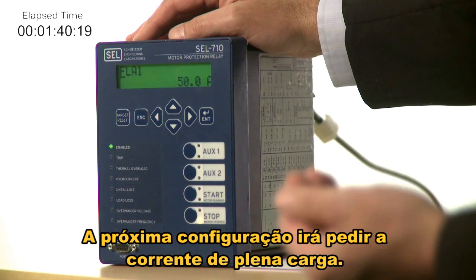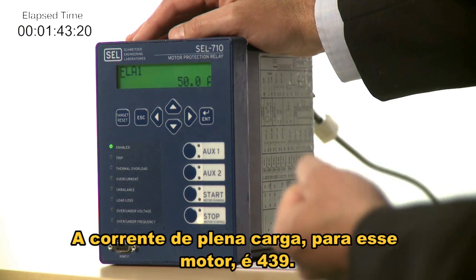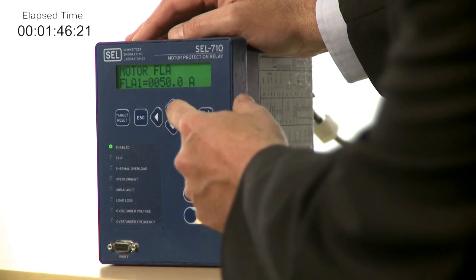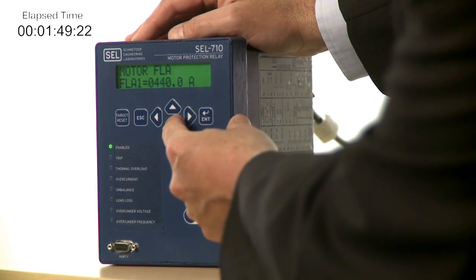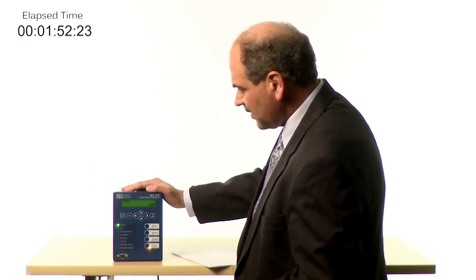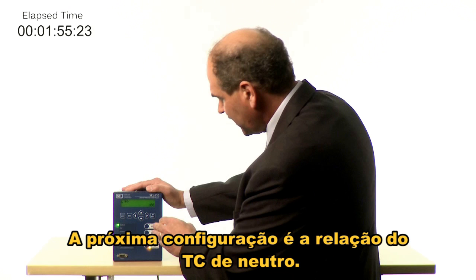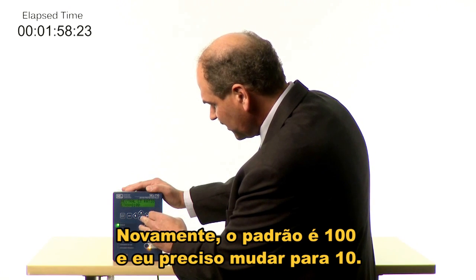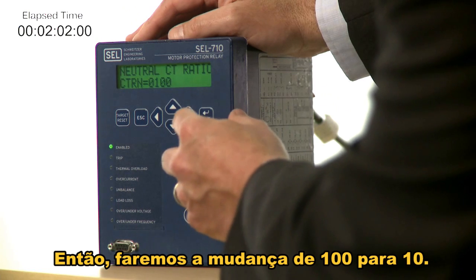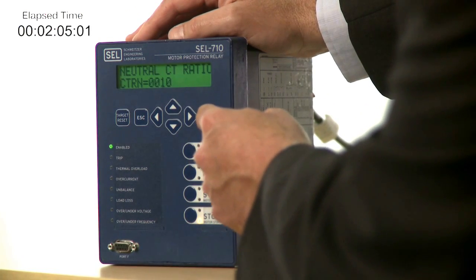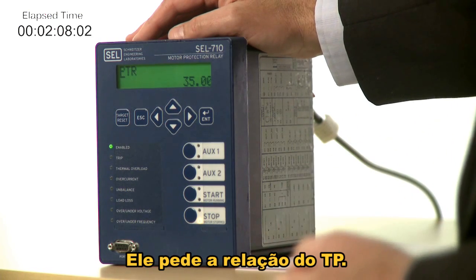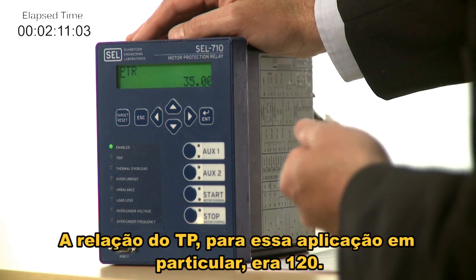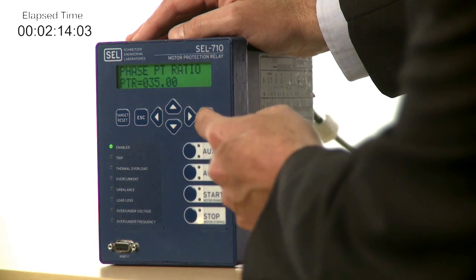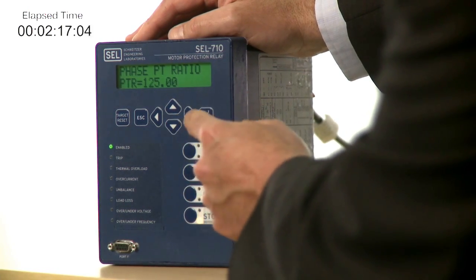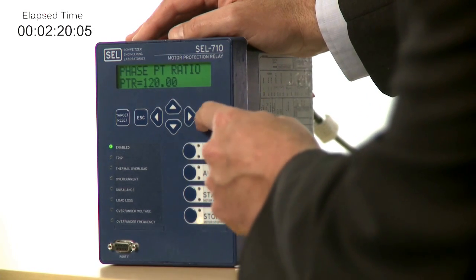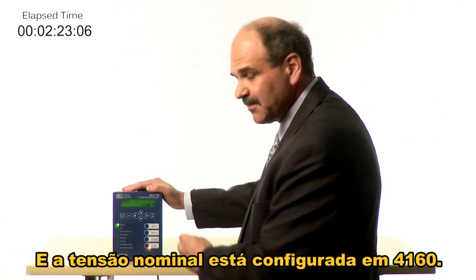The next setting it's going to ask is what's the full load amps. The full load amps for this motor was 439, so we're going to make that change. The CT ratio for the neutral is the next setting, and again the default is 100, and I need to reset that to 10. So we're going to make the change from 100 to 10. As for the PT ratio, the PT ratio for this particular application was 120. And the nominal voltage is set for 4160.